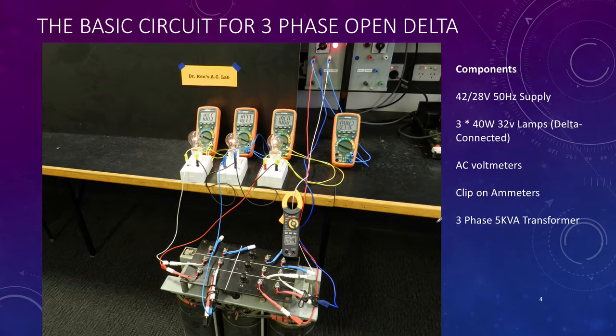Here's our connecting-up arrangement. We have our supply and our lamps as loads. You can see down here the C-phase windings are not used. We've only used A and B. On the secondary, the A and the B. This transformer has a ratio of about 4 to 1, so if I put 40-odd volts in, I'm only going to get about 10 volts out. That's our connection.